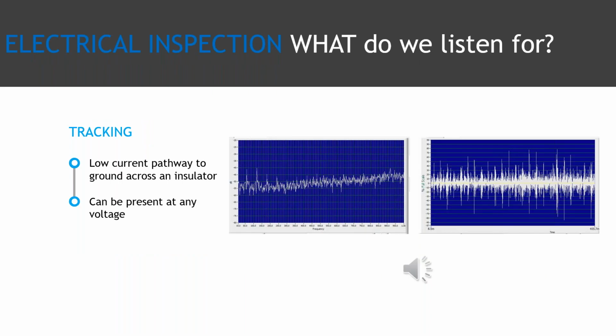With tracking, tracking has taken it a little step further. It's not just ionization that's dissipating into the air. It's actually found a low current pathway to ground. So we're going to get a little more damage. It's going to be a little different sound pattern. We may get a couple of harmonics on the FFT spectrum, but we're going to mostly get a lot of frequency content. What's really telling is the time waveform. On the time waveform, we're going to see uneven heights of the discharges. We're going to see uneven time spacing of the discharges, and some of them will last longer than others.